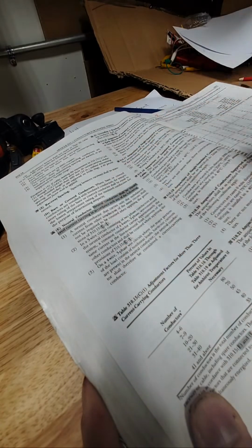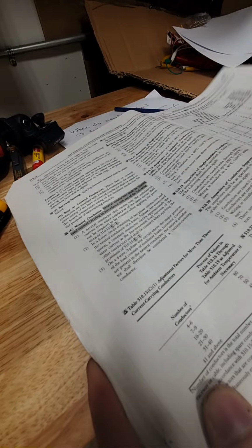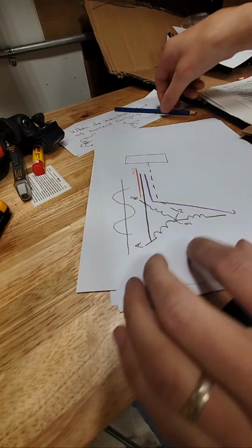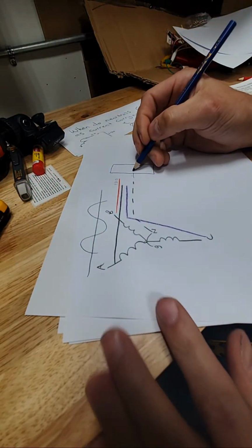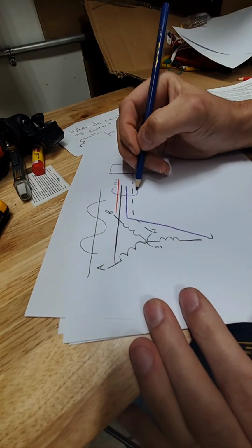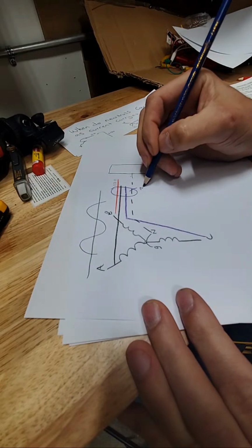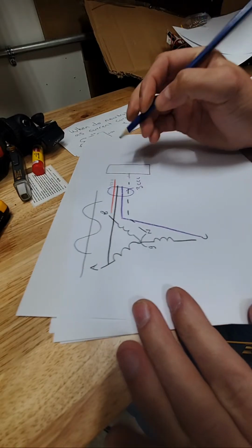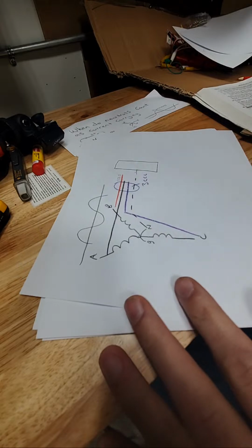But in a normal system, when you leave your panel, this neutral is not going to be carrying anything to your junction box. But these three hots, so when you're counting your current carrying conductors, this will count as 3 current carrying. 3 CCC, 3 current carrying conductors.